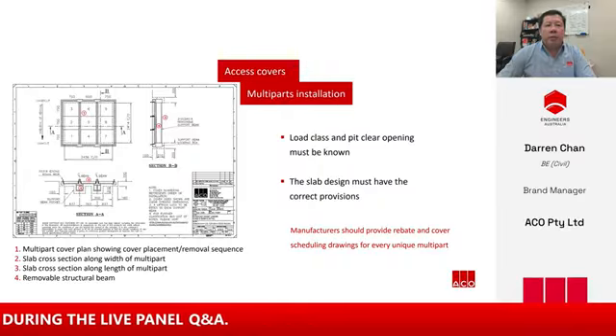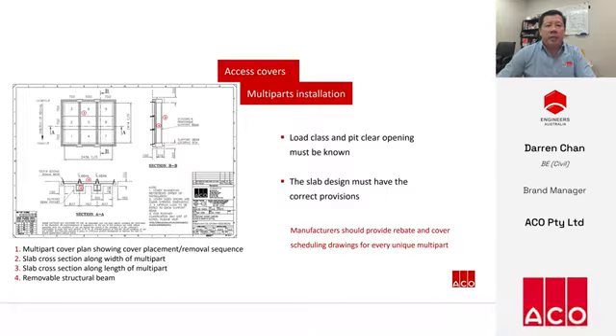Multi-part installation requires careful planning. The load class and pit clear opening must be confirmed, and the slab design needs to provide for the locations and depths of the beams and frames for the multi-part. To allow for this, manufacturers must provide rebate and cover scheduling drawings for every unique multi-part - you cannot install one without it. A rebate drawing must show the four essential elements and views described on the slide.